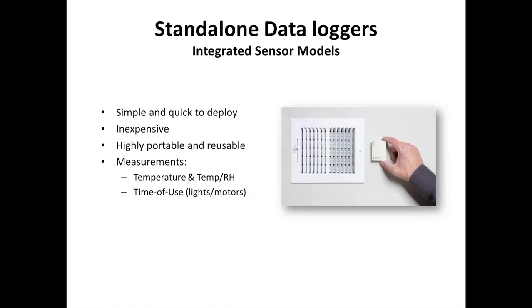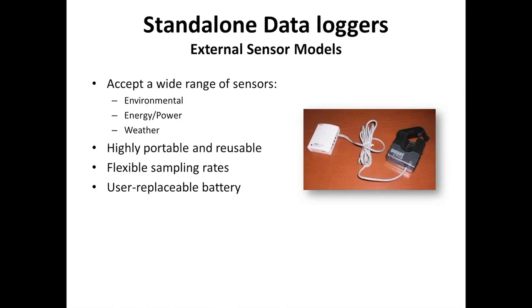These are probably the most common sensors that we use. They're integrated sensor models. These are basically limited to temperature and humidity, or also time of use, such as lights and motors. These are just a simple install. We use a computer to set them up and stick them out in the field. They'll record at different intervals, temperature and relative humidity. It really gives us feedback into how a building's performing, or how a specific system is performing.